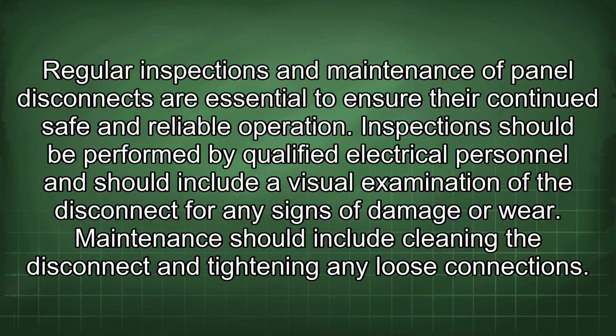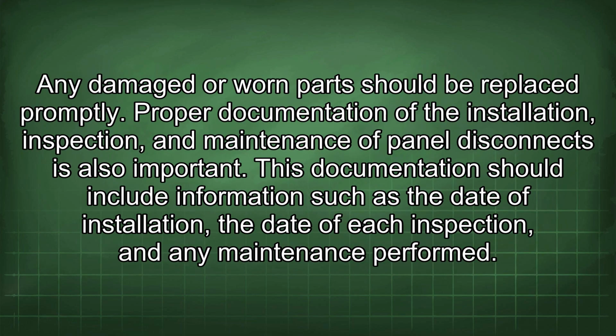Regular inspections and maintenance of panel disconnects are essential to ensure their continued safe and reliable operation. Inspections should be performed by qualified electrical personnel and should include a visual examination of the disconnect for any signs of damage or wear. Maintenance should include cleaning the disconnect and tightening any loose connections. Any damaged or worn parts should be replaced promptly.